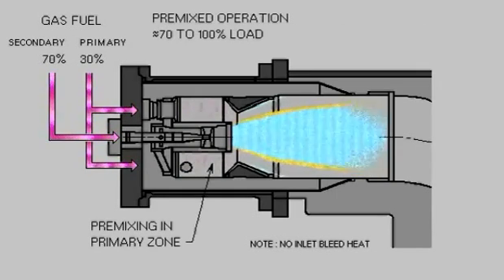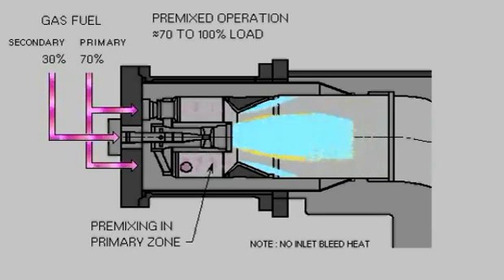The pre-mix mode: Fuel is supplied to both the primary and the secondary nozzles. However, flame is in the secondary stage only. This mode of operation is achieved at and near the combustion reference temperature design point. Optimum emissions are generated in premix mode.